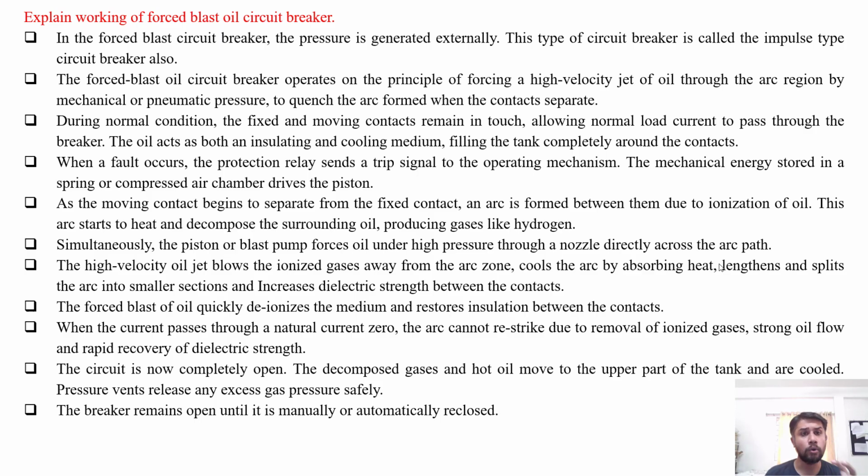The forced blast oil circuit breaker operates on the principle of forcing a high velocity jet of oil through the arc region by mechanical or pneumatic pressure to quench the arc formed by the contact separation, meaning when the contacts are separated, the arc is struck in between.